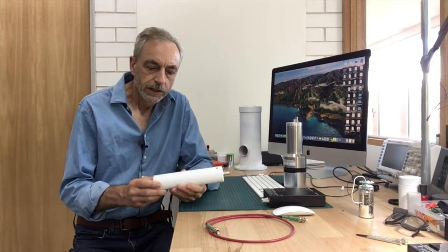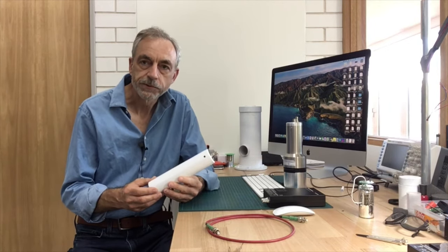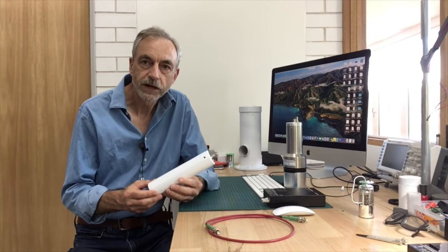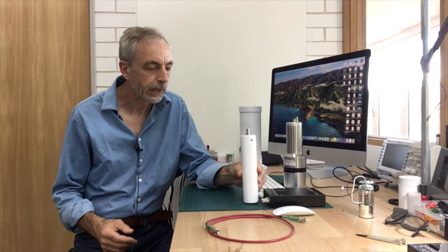Today I'm going to do the experiment with what I call a general purpose detector. This is a 1.5 inch sodium iodide detector. This is something that comes up very often with beginners. I get asked what's the difference between a one and a half inch detector, two inch detector and three inch detector, and the only difference is what we refer to as the efficiency. The efficiency is a measure of how efficiently the detector or the crystal absorbs the higher energy gamma rays.